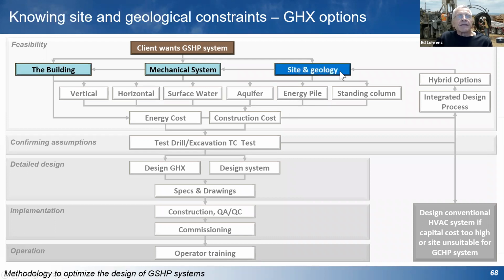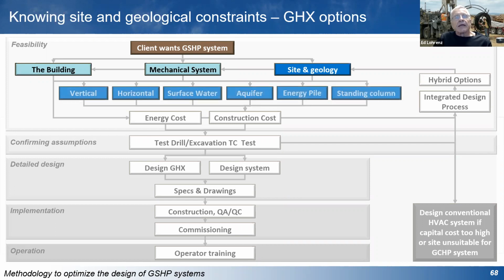And then we have to deal with the site. So we need to know what the geology is. What piece of dirt do we have to work with, and what can it deal with? And what configuration of ground heat exchanger would fit on that property? In this case, the land area available wasn't good. There were only a couple of good options. Vertical ground heat exchanger. We didn't have room for a horizontal.